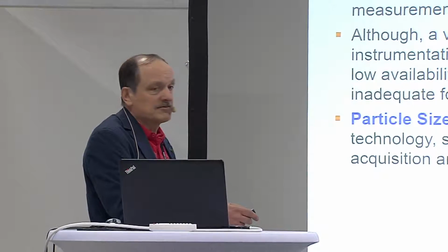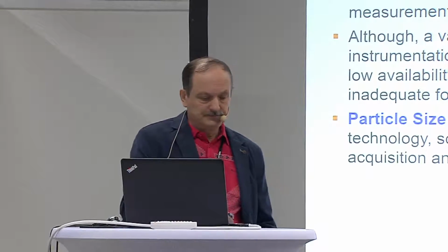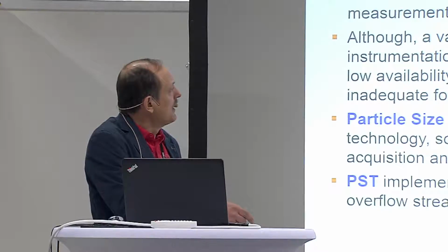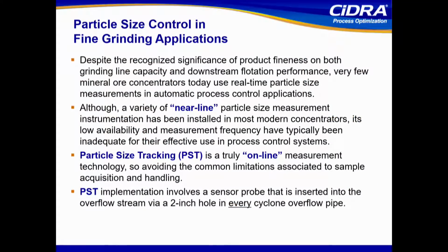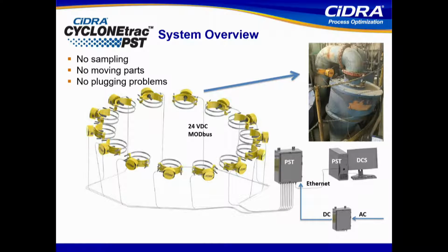Real-time producing measurement results every 4 seconds. Installation is very easy. You just drill a 2-inch hole there and put the sensor in. And that's how the whole system looks when a battery is instrumented. So every hydrocyclone overflow has its own sensor. They are connected to a junction box that collects the signals to the PST computer, and that is then linked to your DCS system, the customer DCS is available there. In addition to that, there is a cloud connection available, and CIDRA expertise support available for this.